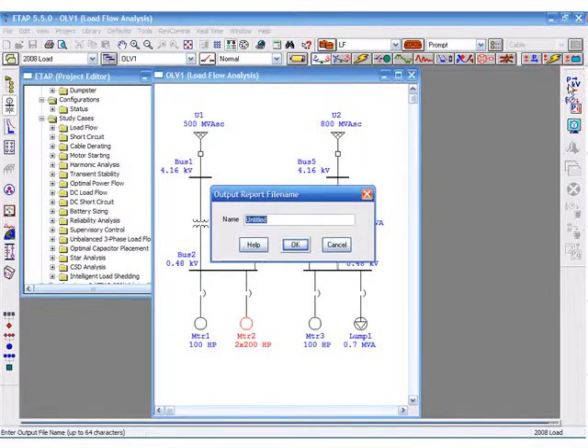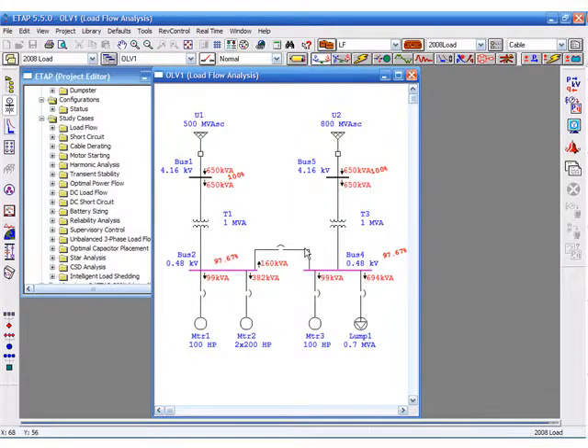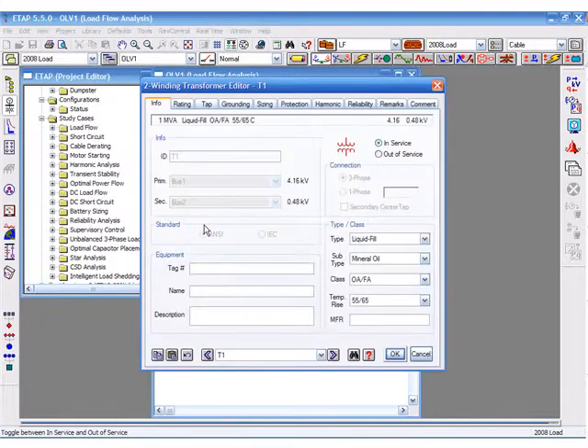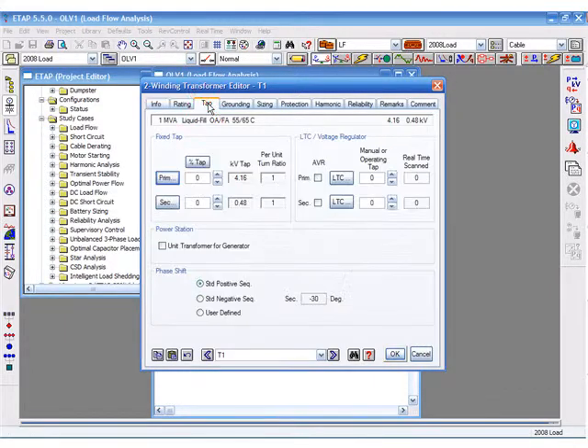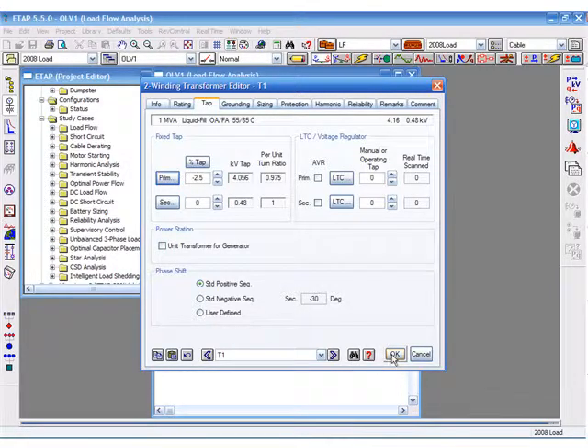If we re-run our load flow case, we notice voltage on bus 2 falls. If we go to the tap page to add one to boost the voltage on the secondary, we can see the improvement.